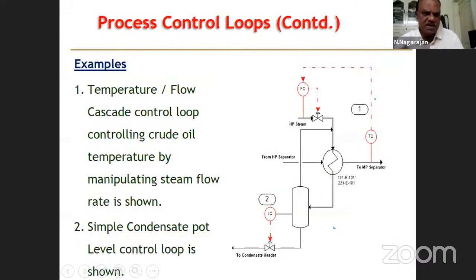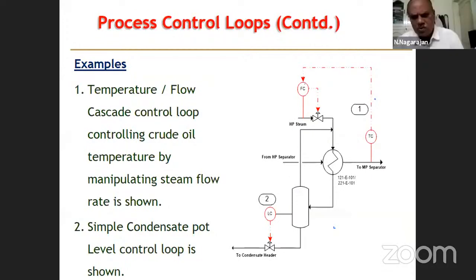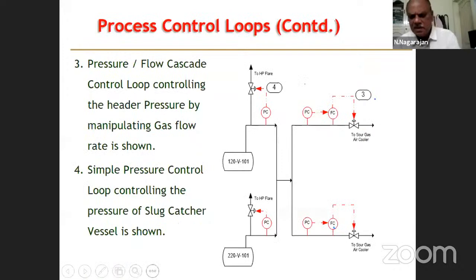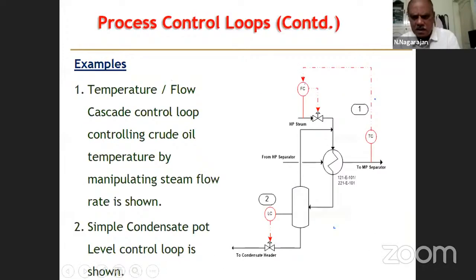And the temperature flow cascade control loop, controlling crude oil temperature by manipulating the steam flow rate, is shown. So this we have seen. I think heat transfer control is the main thing. Crude oil is the main process stream. So the main process stream is the hydrocarbon crude oil coming through the heat exchanger, and you use steam to heat the crude oil. The steam condenses, and the condensate is trapped in a condensate pot that is sent back to the steam system.